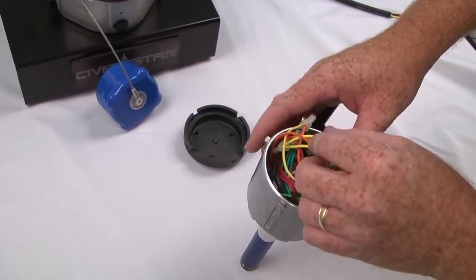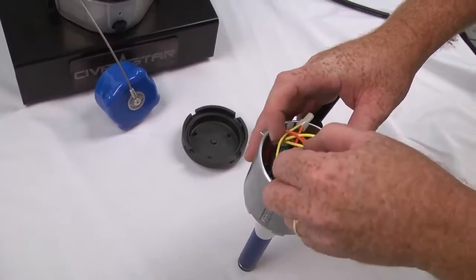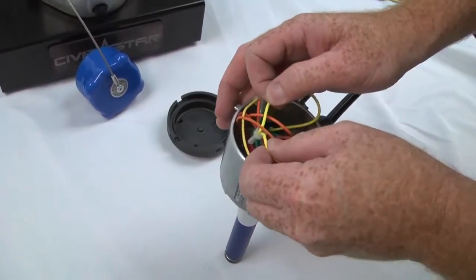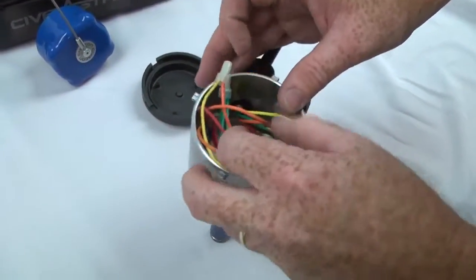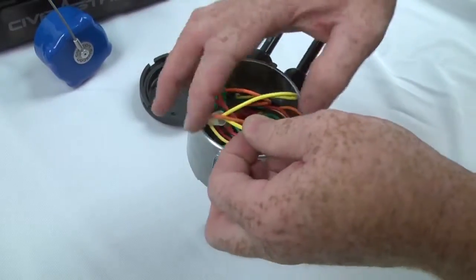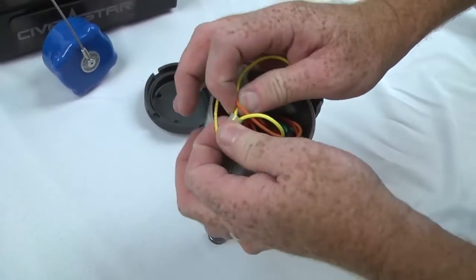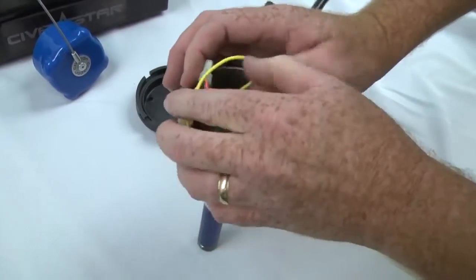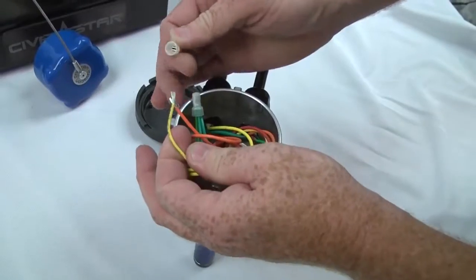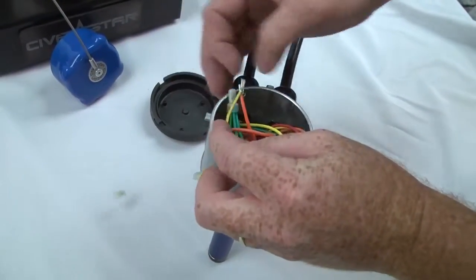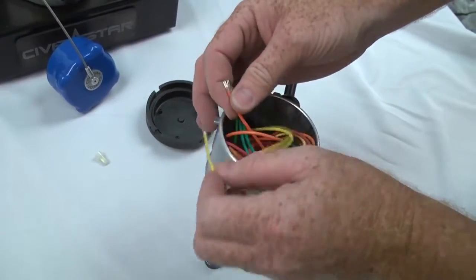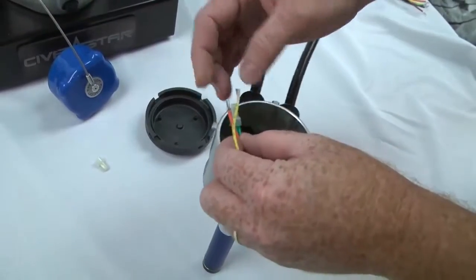Be sure to check all crimp connections for being properly crimped and free from corrosion. As you can see, these are free from corrosion for our demonstration. Give each connection a pull test to make sure they're crimped properly. Like that one right there that was easily removed, it appeared to be crimped, but they pull apart, and that could be causing your fault.